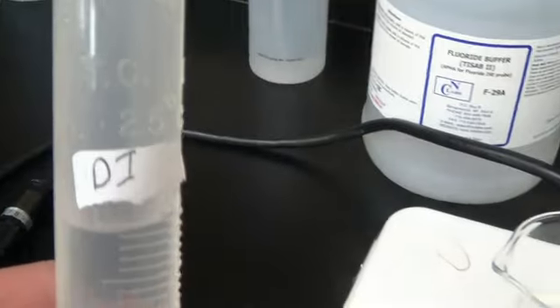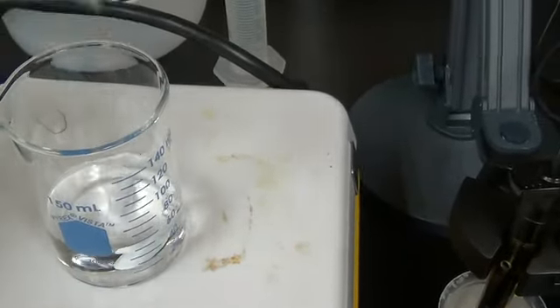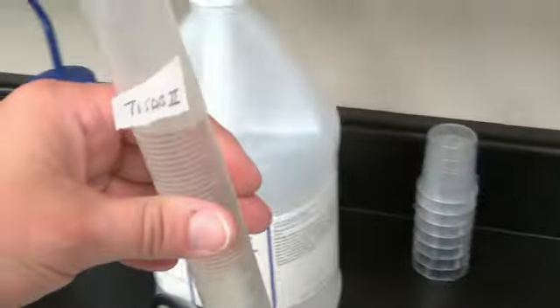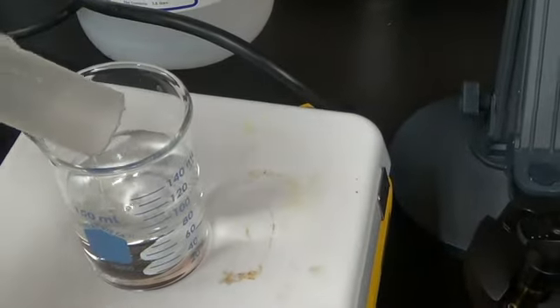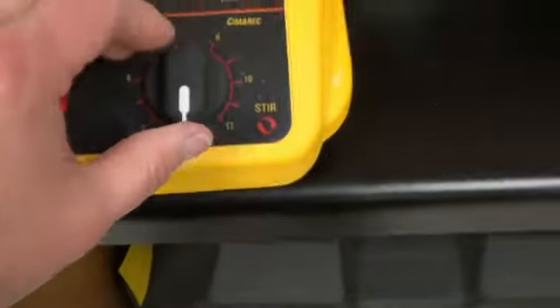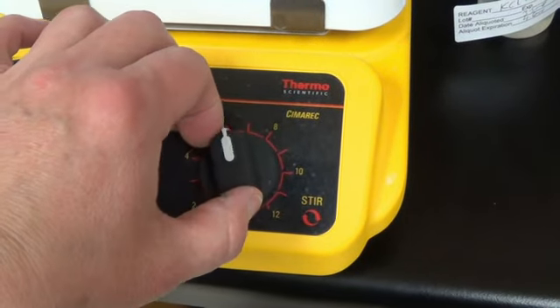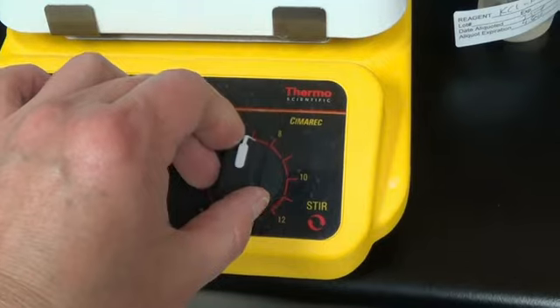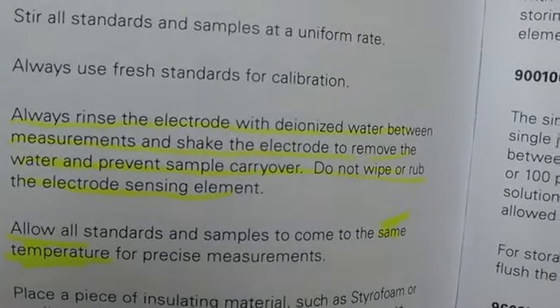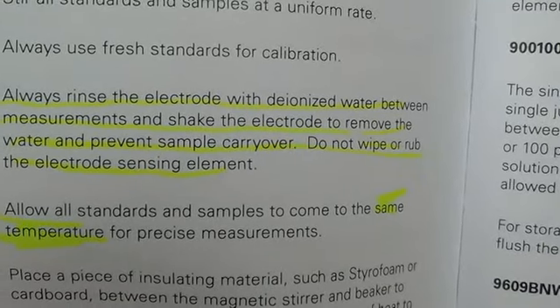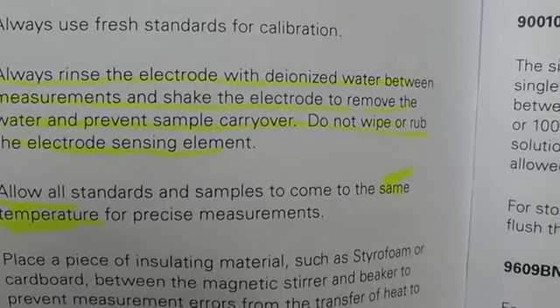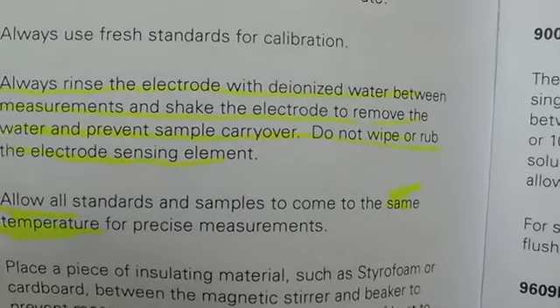So I have my DI water, 50 ml of DI water. And I add my 50 ml of TISAB2. Turn on the stirrer. So that is mixing. I want to make note on the next page under measuring hints. It says to always rinse the electrode with DI water between measurements and shake the electrode to remove the water and prevent sample carryover. Do not wipe the electrode sensing element.